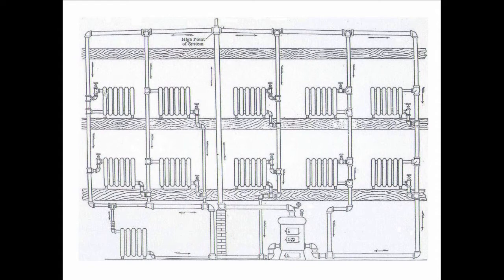So the steam people had a dangerous thing to sell and the hot water people had something very safe, but it was expensive because you had two pipes to every radiator and the pipes had to be large and they had to be the same size. So there was a lot more piping. They were limited to 180 degree water. If they went any hotter than that, it was liable to boil. So the temperature of the radiator was less, so the radiator had to be larger than the steam radiators that went in by the steam fitters. So much more expensive, but safer.